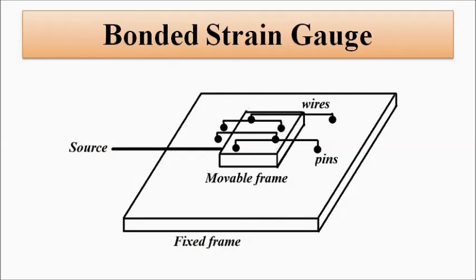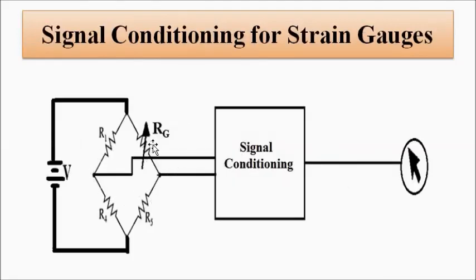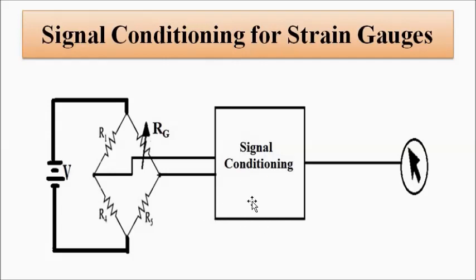Whenever there is a change in resistance, the Wheatstone bridge becomes unbalanced and there will be a current flow. This signal must then be passed through proper signal conditioning circuitry to amplify the signal, linearize the output, remove unwanted noise and interference signals, and perform frequency response matching, so that we get the desired signal without any loss. Then it is given to a digital readout, LCD display, or pointer scale arrangement.